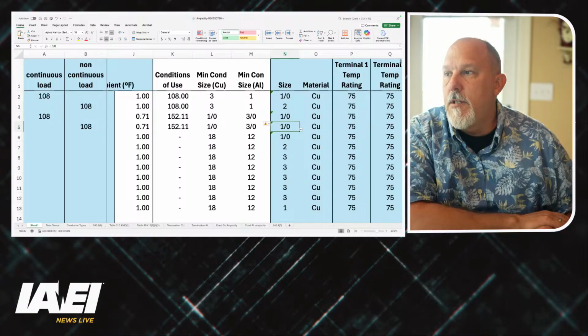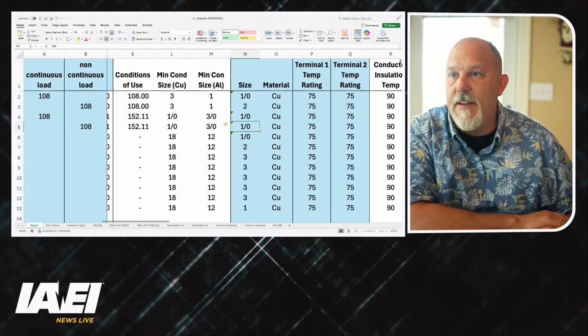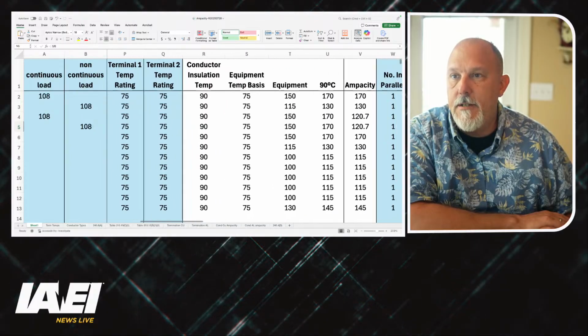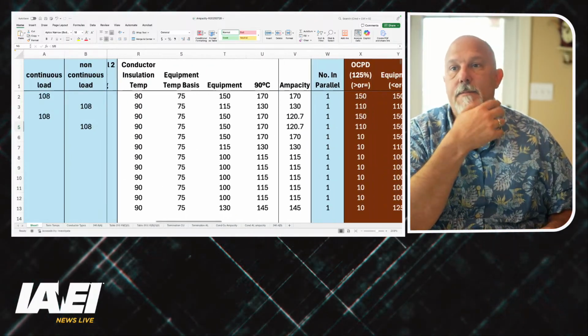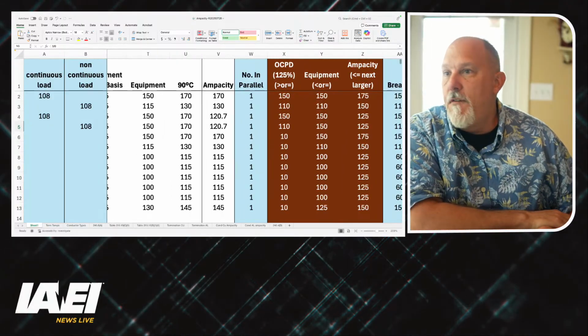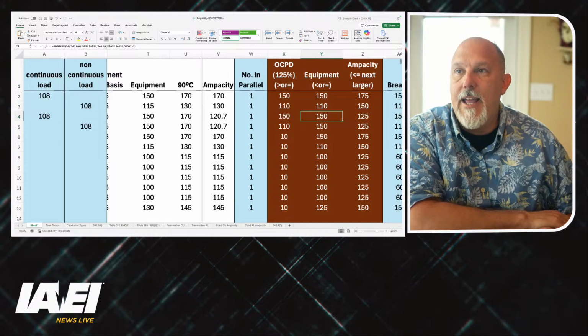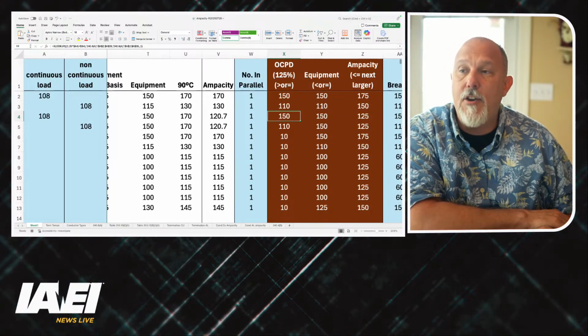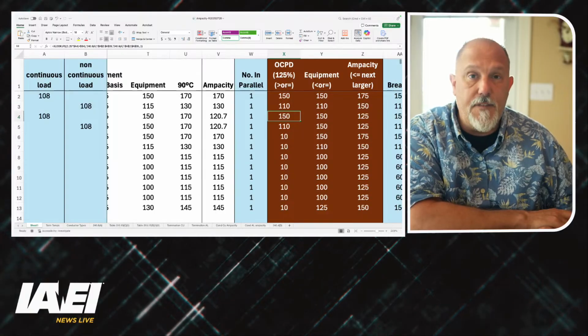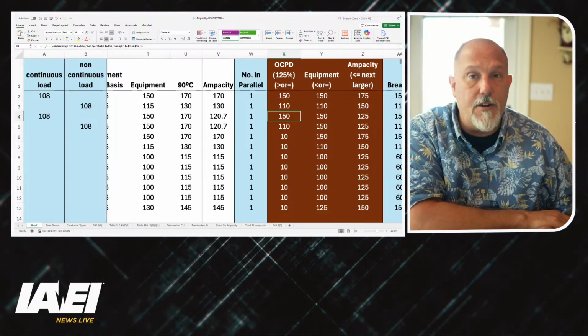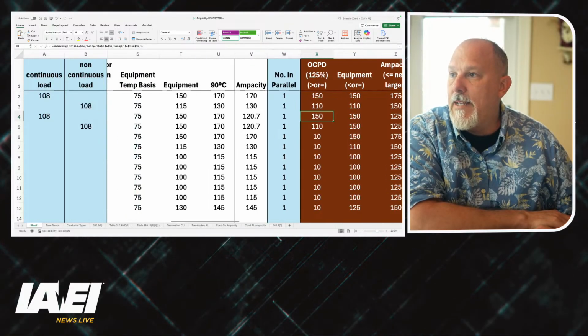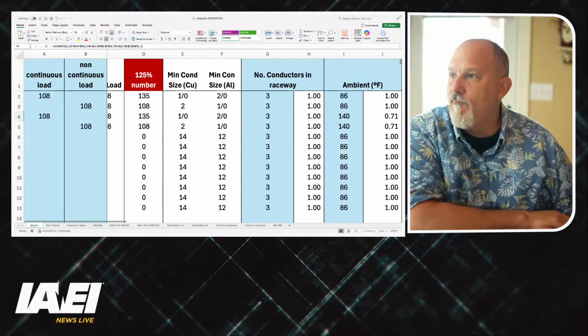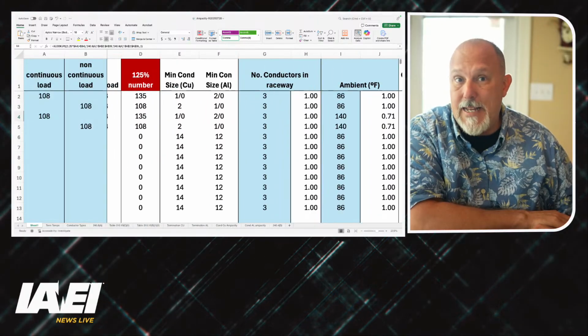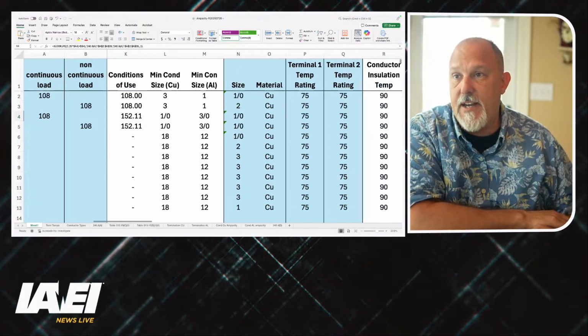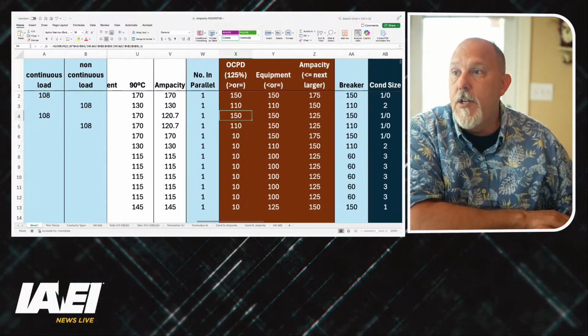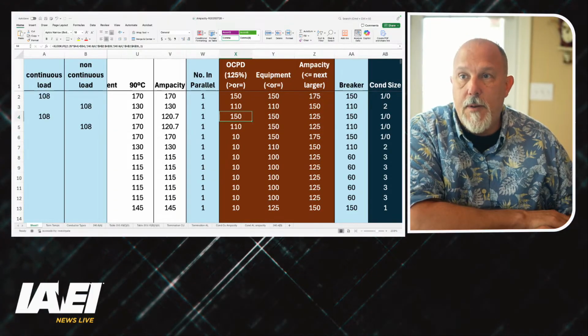All right. So 75 degrees C, 90 degrees C insulation. So now, here's my criteria. For the continuous current, I have 150 amps. My overcurrent device has to be at least a 150 amp breaker to be greater than or equal to the 125% number. Why is that? What's the continuous current? 135 amps. I can't be less. I go to the next larger size from 135, and that would be a 150 amp breaker. So, and that's the same as it was before. So I'm going to pick 150 here.